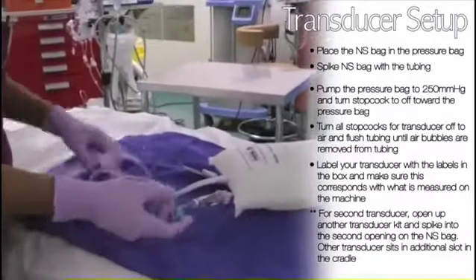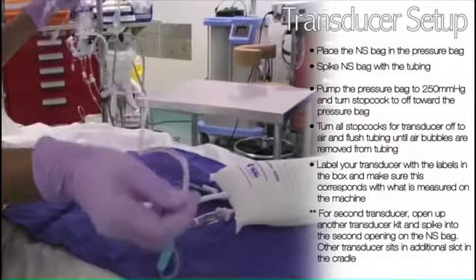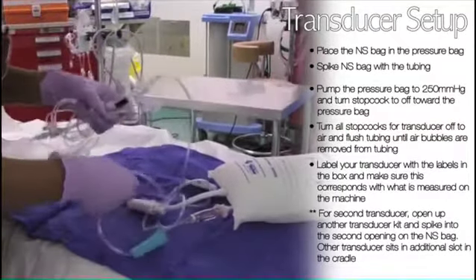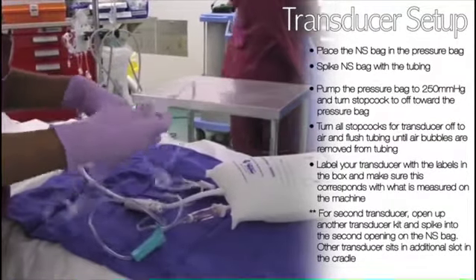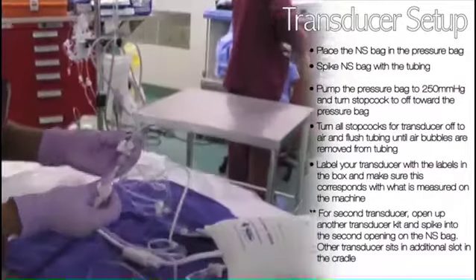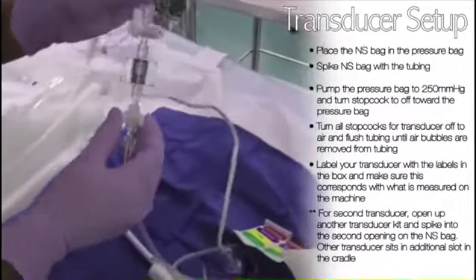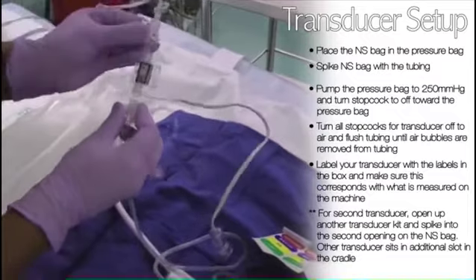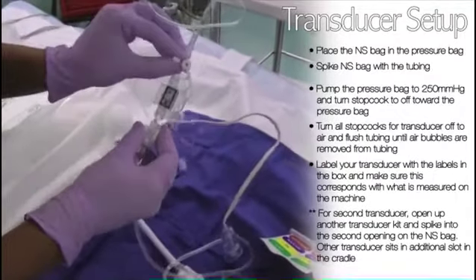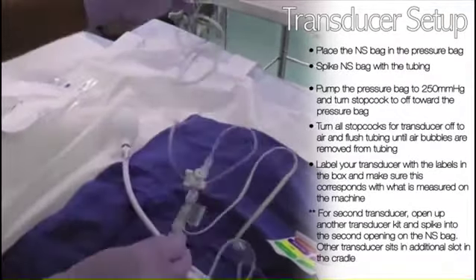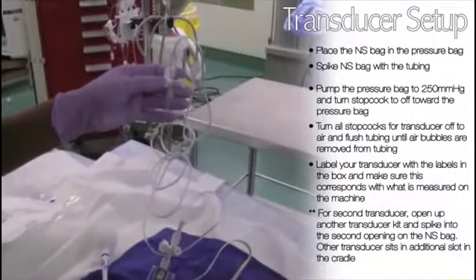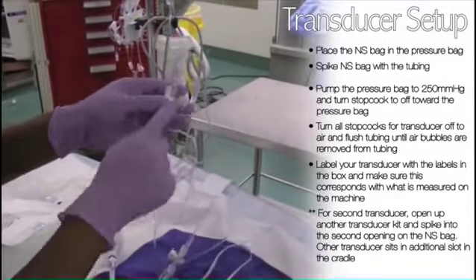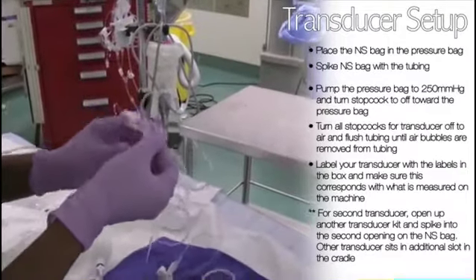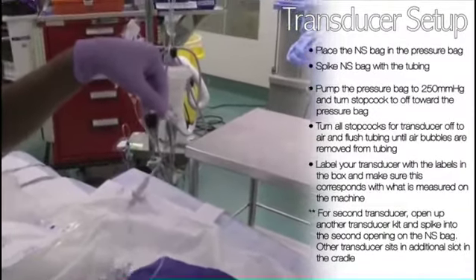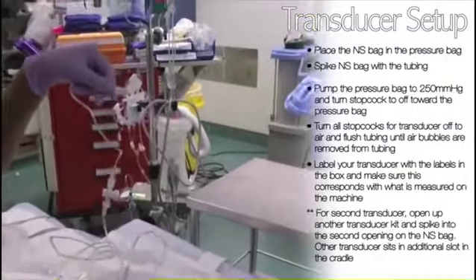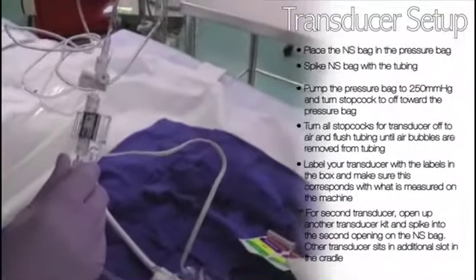Finally, to make sure that you are not going to give your patient any air, you have to prime the tubing. Every transducer has a flush line. You flush and turn this off to this site, flush the line till it's off to this site and the air bubbles are out, and finally flush to the end and examine the tubing to make sure there's no air bubbles.